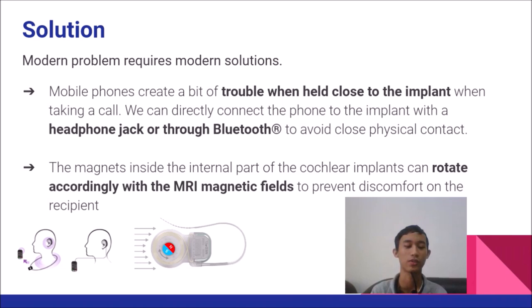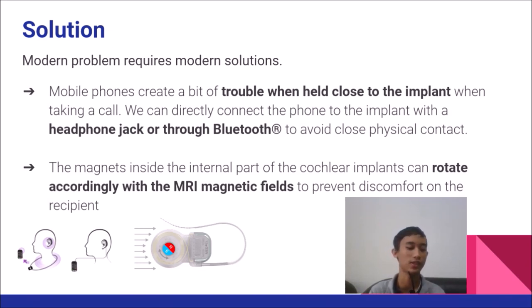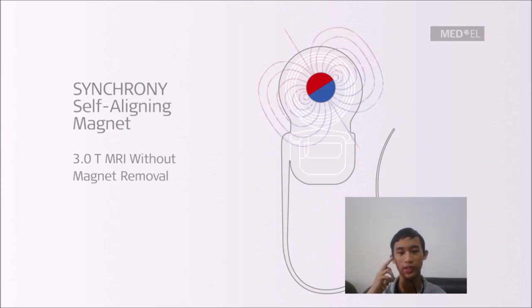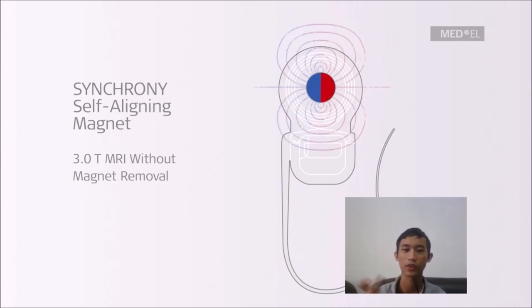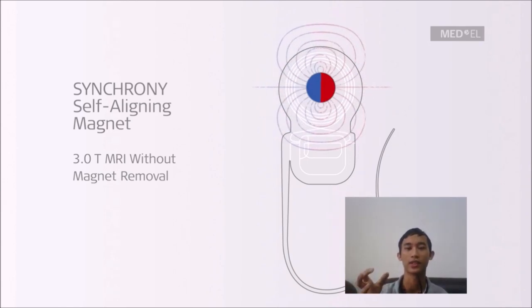There are some things we can do to mitigate that. One is getting an MRI-compatible cochlear implant — basically, something that allows you to go into an MRI with the implant in your head and it would be fine; you wouldn't have to remove it or undergo surgery. You can operate like a person who doesn't have an implant. These implants have caveats, being rated up to 1.5 Teslas or 3 Teslas depending on the type. One approach is getting the inner magnet inside the cochlear implant to freely move according to the MRI's magnetic field, so it doesn't interfere with the wave.